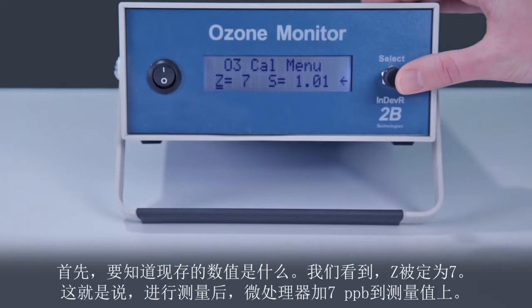First, note what the current value is. We see that Z is set to 7. That means that after making a measurement, the microprocessor adds 7 ppb to the measured value.